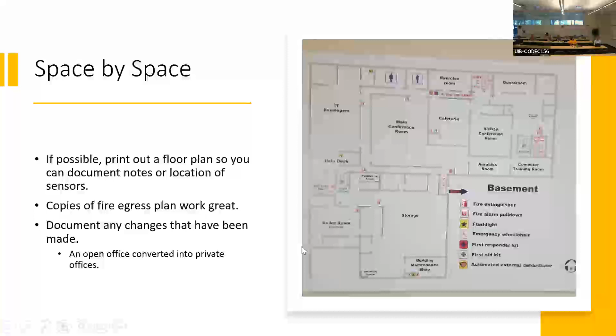Verify the location of the space via the floor plan. I like to have a floor plan as well as my sheet I'm filling out, because I can document space name changes—this one has an occupancy sensor right there, this has supply for HVAC, this has return for HVAC. Another method is taking a highlighter and outlining the floor plan where the HVAC zones are, so you can differentiate and keep track as you go. That also helps when I meet up with someone doing HVAC and compare the zones I got to what they saw on the roof, tracking the rooftop to the appropriate zone.